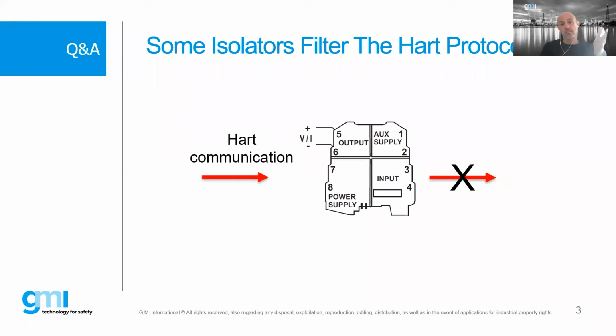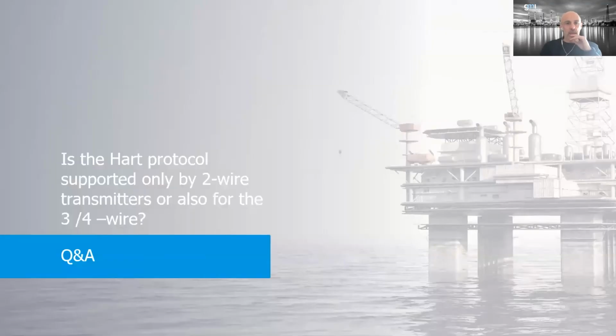Yeah, the barriers isolators are for 4 to 20 milliamp signals, but if HART is specified, the modules will transfer HART. Otherwise, it will be cut because there is a complete isolation between input and output on the modules. Okay, so another question: is the HART protocol supported by 2-wire transmitters also for the 3-4 wire?